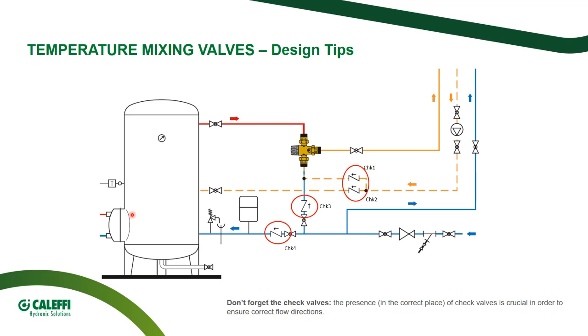So let's start from the check valve. That is one of the most important accessories around the mixing valve. So don't forget the check valves. In the typical diagram of a medium-big mixing valve, which can be digital or thermostatic, we have at least 4 check valves. We identify them as check valve number 1, 2, 3, and 4.